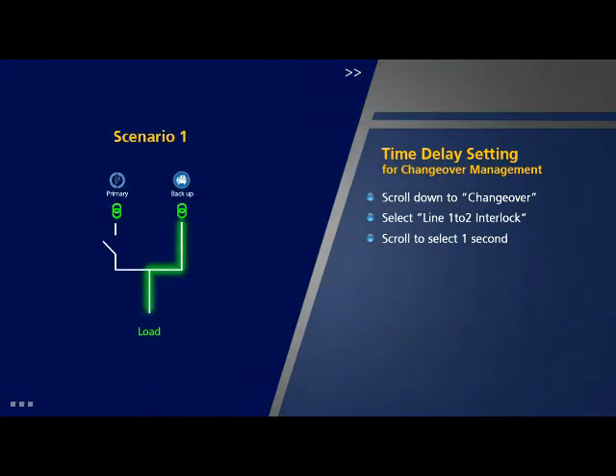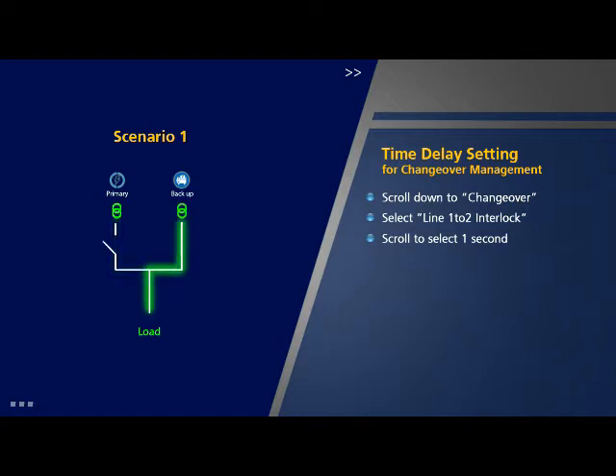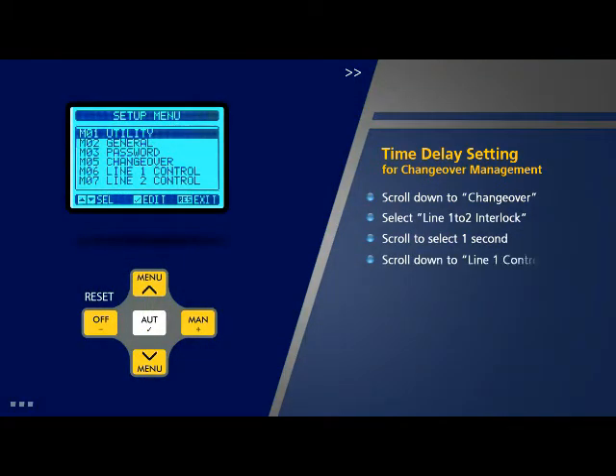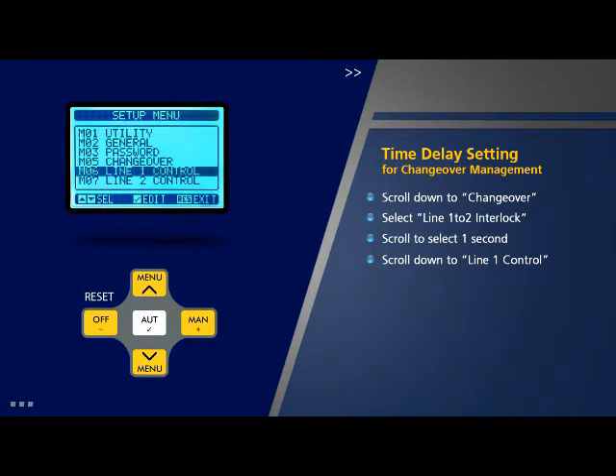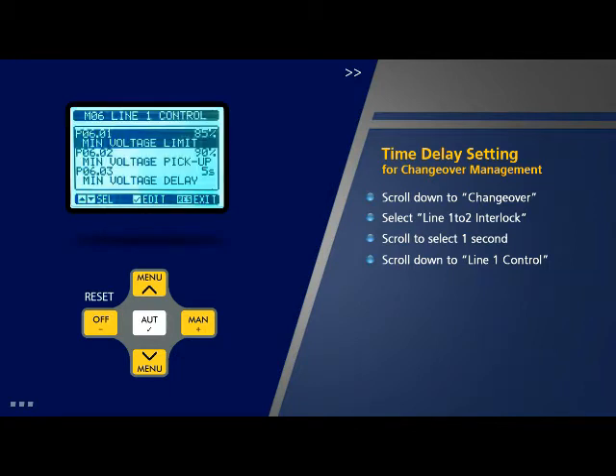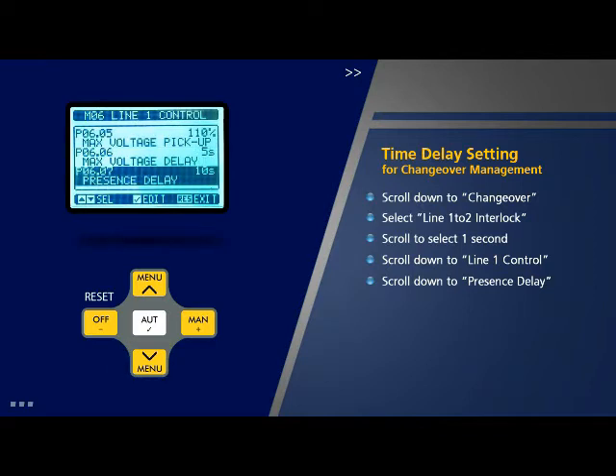Scenario 1: The load is connected to source 2 (DG) which gets shutdown. The load will be connected to source 1 (utility) after the set delay. In this case the duration of delay should be as short as possible since there is an urgent need to supply power as the load is not energized. The default value of the delay is 10 seconds. The procedure is: scroll down to parameter 6 of setup menu which is 'Line 1 Control' and press OK. Scroll down to parameter 7 on this page which is 'Presence Delay'.